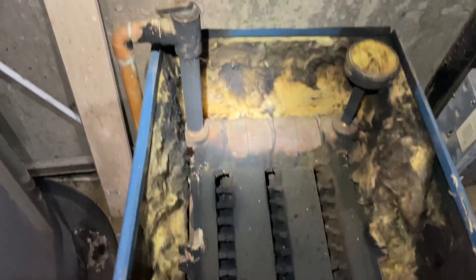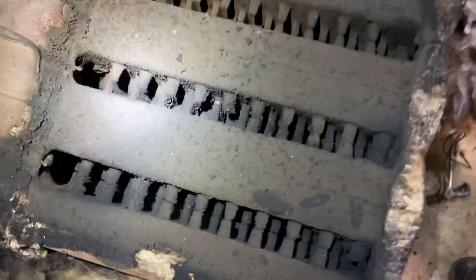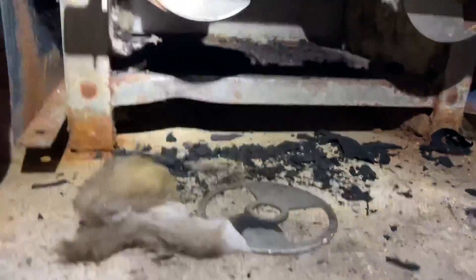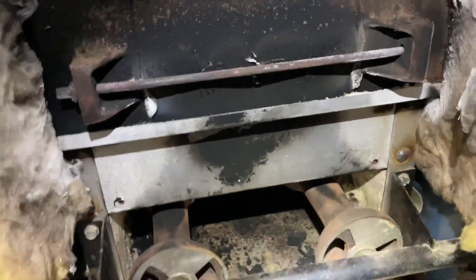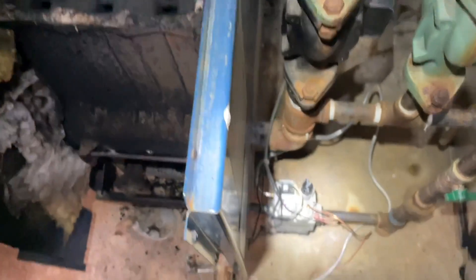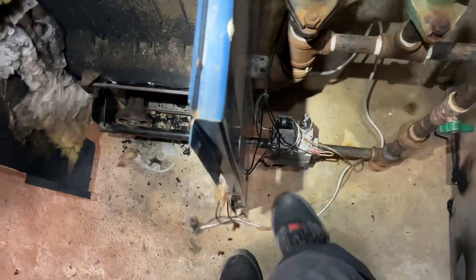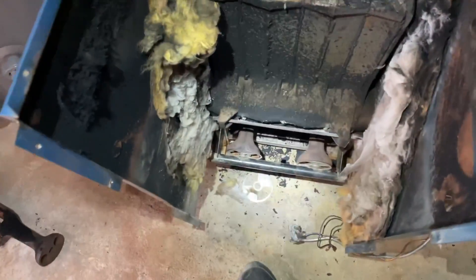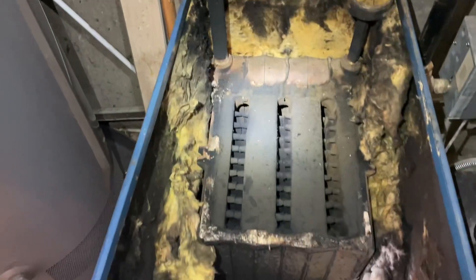Just got back with the soot vac. Holy — what did they do when they cleaned this thing? Oh my god, what a disaster. We're gonna scrub this down. I need to dial down the gas valve, change that out, pilot tubing, thermocouple, rollout switch. Let's get scrubbing — I already did the first section.